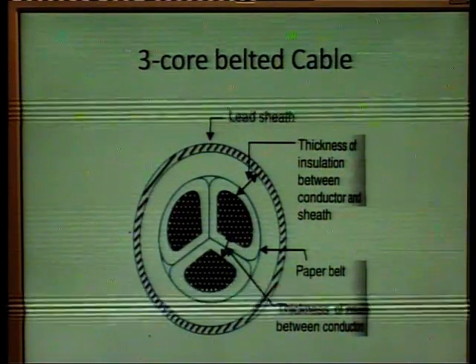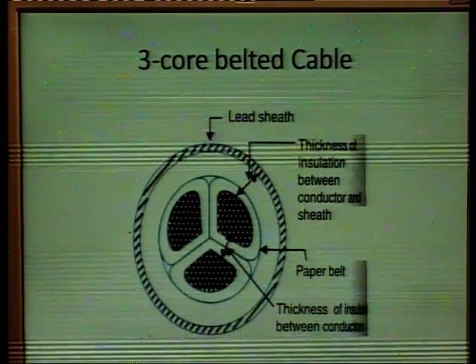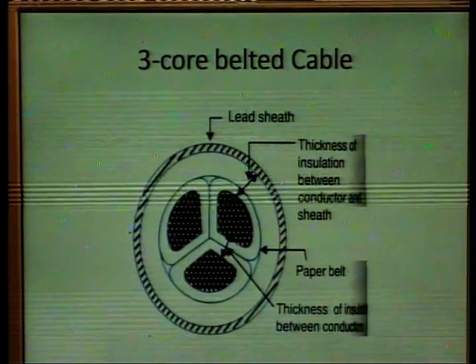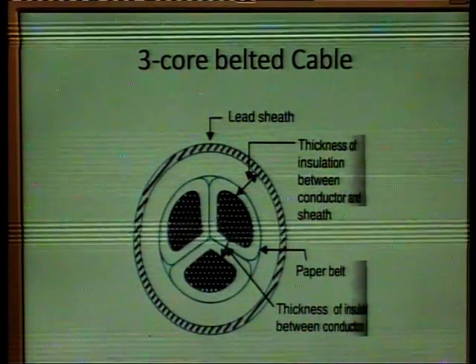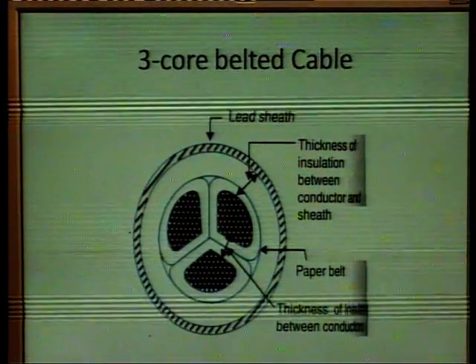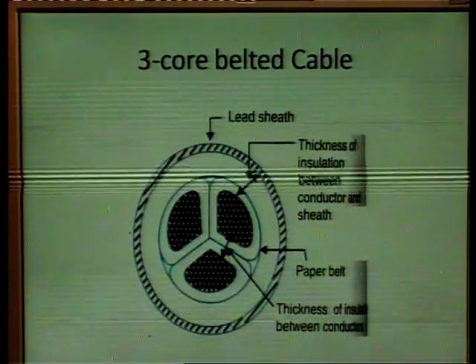So this is the 3 core belted cable. Lead sheath is there, and the thickness of the insulation between conductor and sheath. Paper belt is there, and there is a thickness of insulation between the conductors.